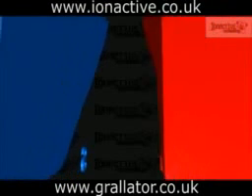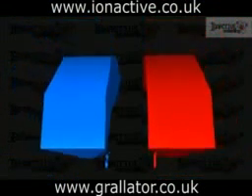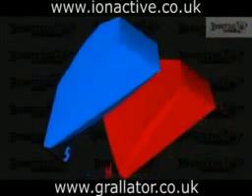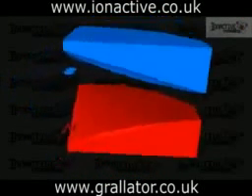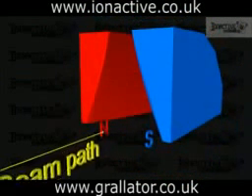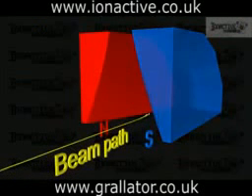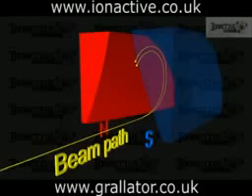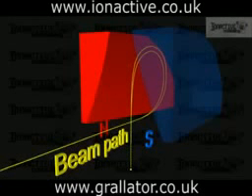To avoid this, a 270 degree bending system was introduced, which uses shaped pole faces that give a field that grows in strength as the radial distance from the beam inlet point increases. More energetic electrons penetrate further into the bending magnet but are then subjected to a higher magnetic field, decreasing the orbital radius. The net effect is to produce a beam that leaves the magnet with all the electrons passing through the same point and moving in the same direction. It is a so-called achromatic bending system.